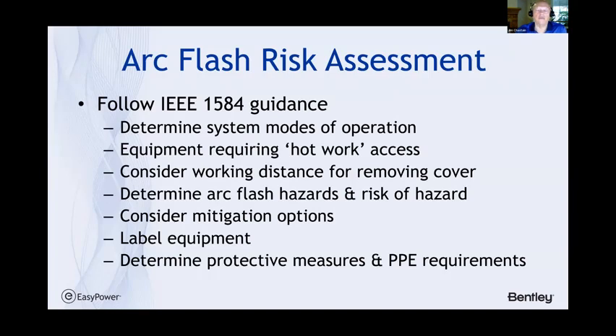You need to consider the working distance for removing the cover. There was a good question in Justin's presentation. The label that goes on the cover or the door of the equipment has a working distance usually determined by the IEEE standards, and usually for 480 it's 18 inches, and it really just gives some advice to somebody in the area who will remove the cover. Many people consider the label to reflect incident energy once you get inside the panel, and it does not. That information, frankly, goes on to a work permit, and so never the twain shall meet.